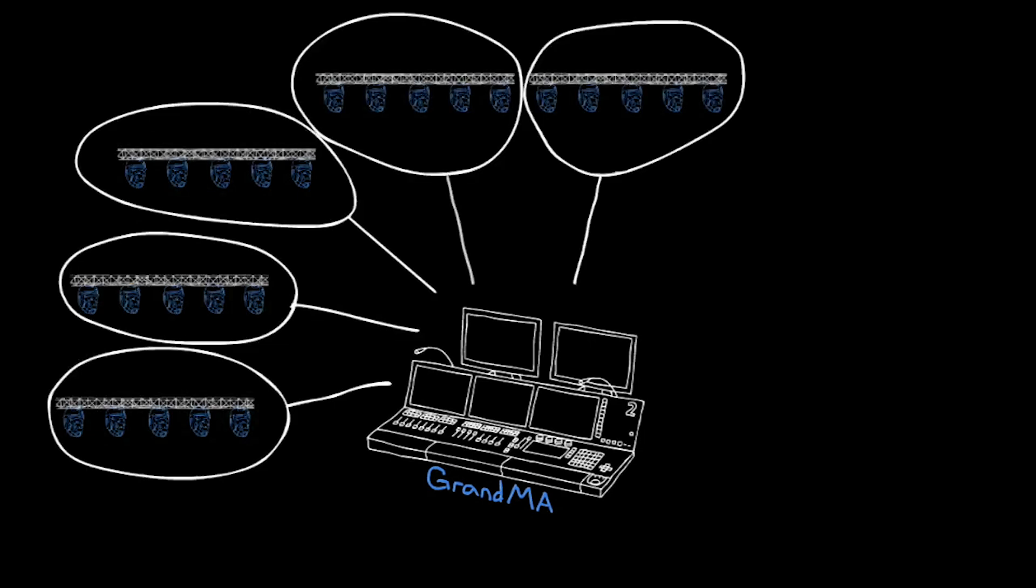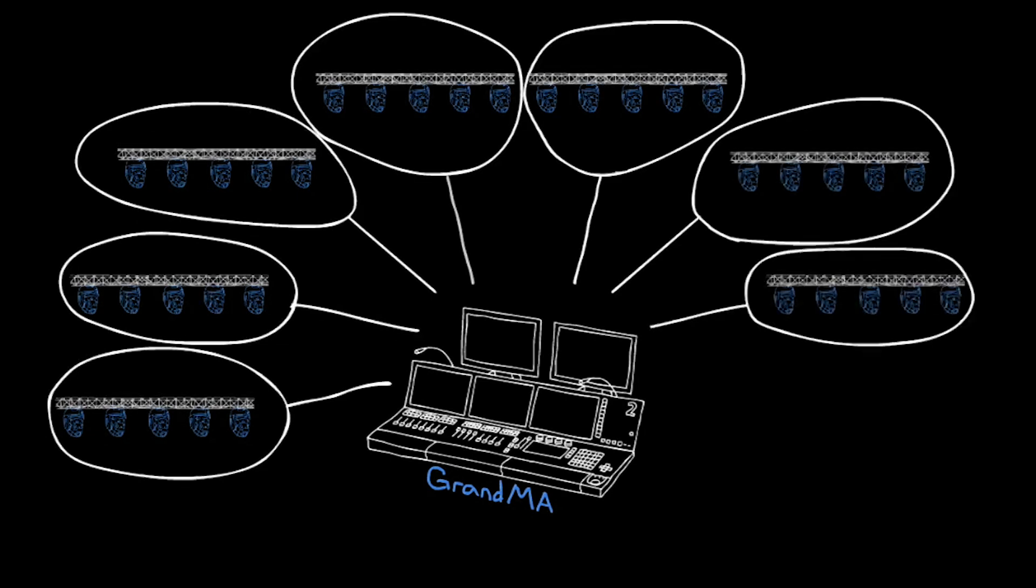Some of these consoles have different universes. Grand MAs can go up to 8 universes of DMX. Each one will be 512 parameters because they get eaten up very fast, and once they are eaten up, you're done. You still need power, so you still need a moving light distro that the fixtures can get power from. It's all data.